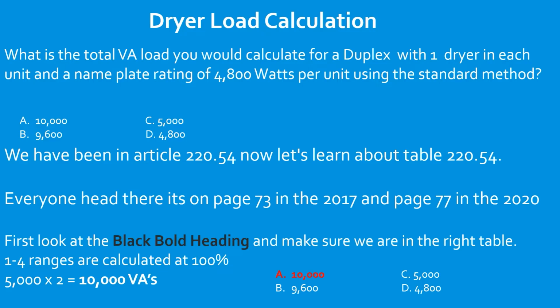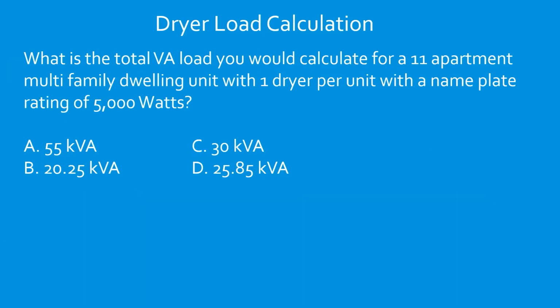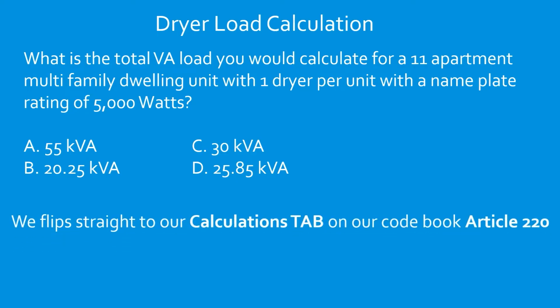Great job. What is the total VA load you would calculate for an 11 apartment multifamily dwelling unit with 1 dryer per unit and a nameplate rating of 5,000 watts? So we have 11 units. Each one has 1 dryer in it. Let's go. I'm going to take you through this process, and I'm going to say it over and over.